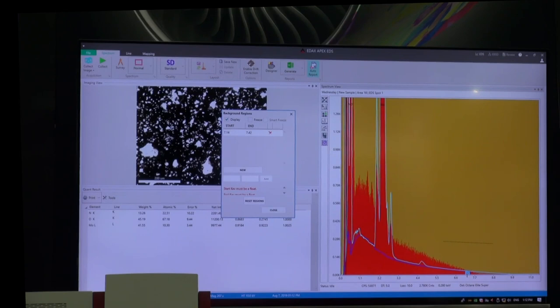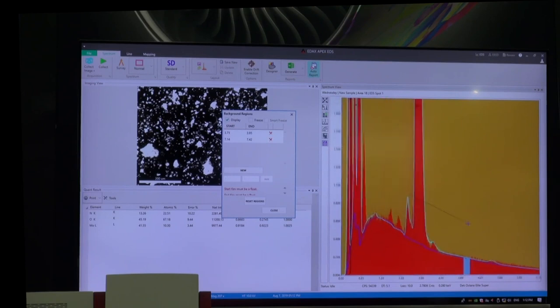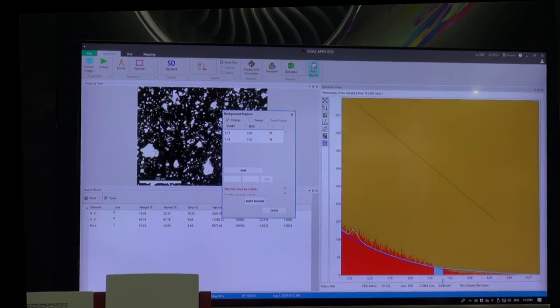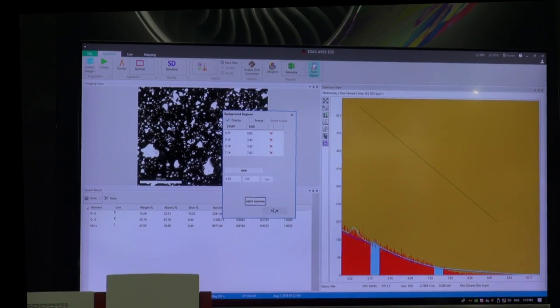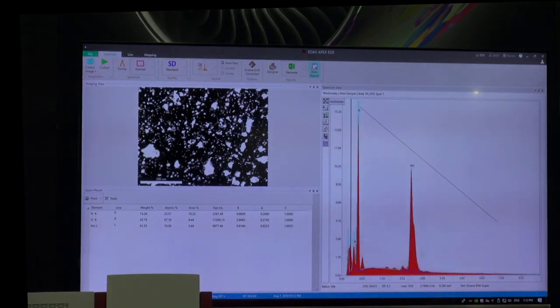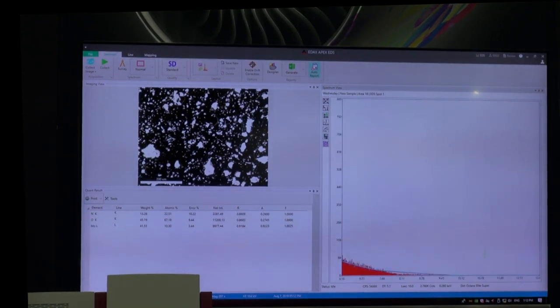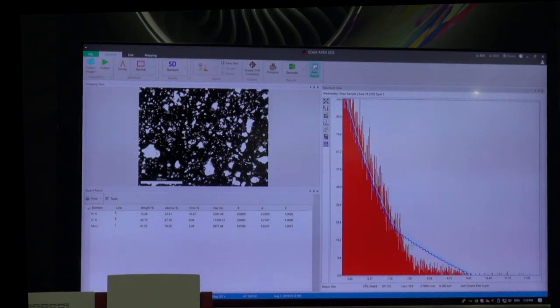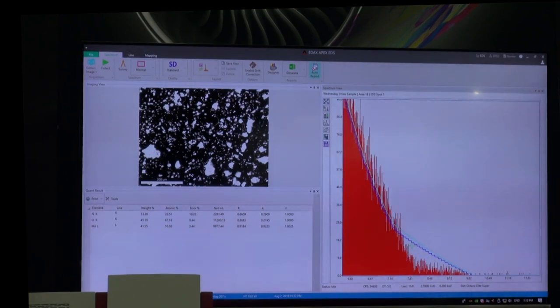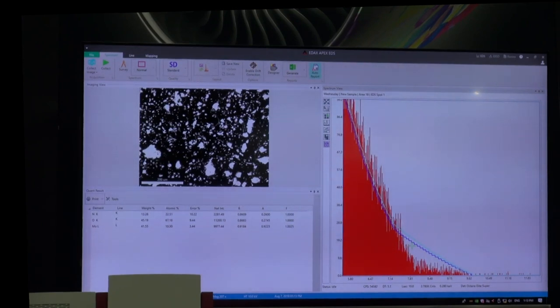I can see I have a significant misfit in my background model using a fit anchor in the relatively high energy range. It's not a problem of the model — it tells you something is wrong with the sample relative to the requirements needed for proper quantification. I can use more fit points to make this work, but give me any curve and enough points to fit it with and I can make it look pretty — that doesn't mean it's correct. Adding more fit points can give a reasonable background tail, but if you don't get a good fit with just one single fit point, there's a good chance you won't get good quant results either.